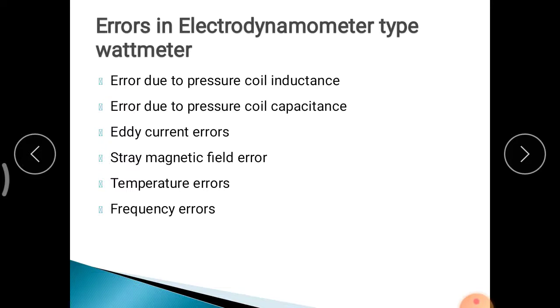Errors in the Dynamometer type Wattmeter: First, error due to pressure coil inductance — the coil has inductance causing lagging of current behind applied voltage, resulting in error. If capacitance is present, current will lead the applied voltage, also causing error. Next, eddy currents are introduced where metallic parts are present, and their interaction with the instrument current causes error in readings.